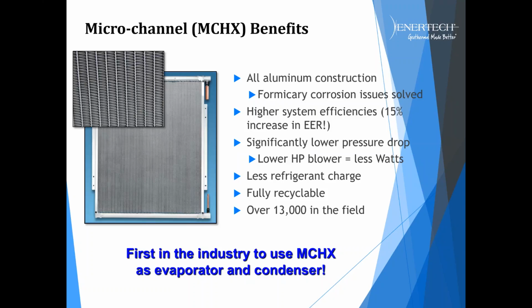We have a significantly lower pressure drop on the fan motor because of the 32 millimeter coil size. It has less refrigerant volume. It's all aluminum, so we've alleviated any formicary corrosion issues. Fully recyclable. It's just been a fantastic product. And again, coupled with the braze plate, we can get a compact design in a very high efficient product.